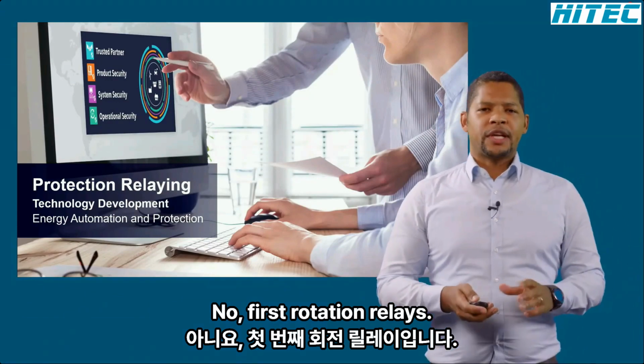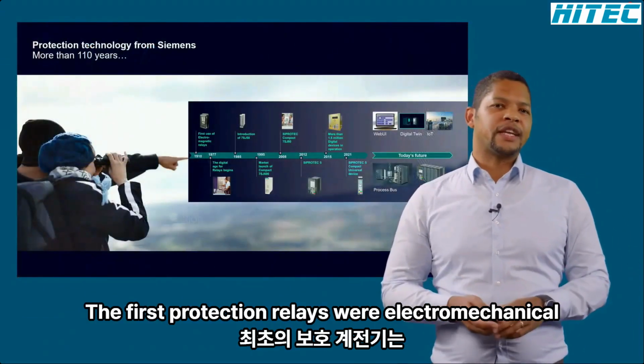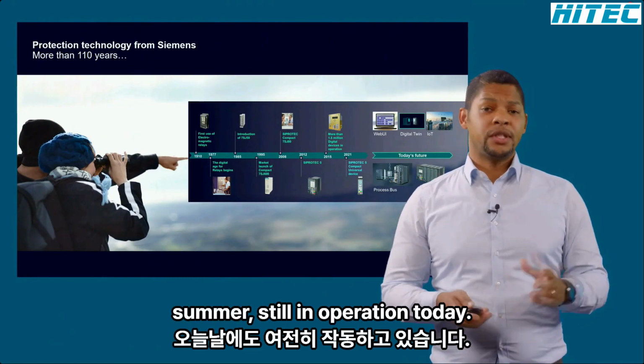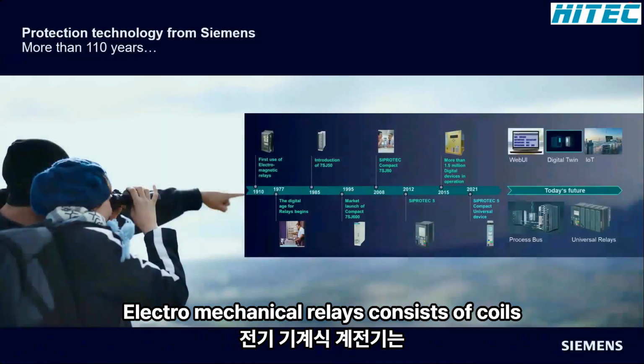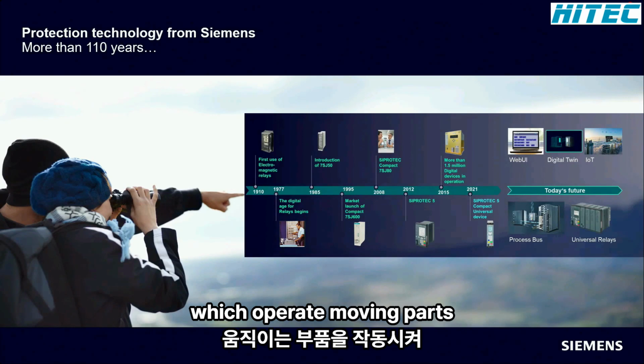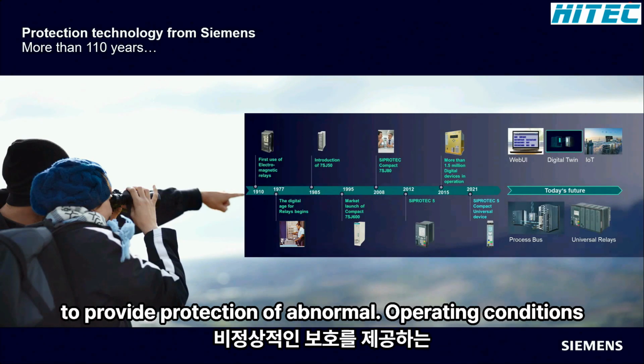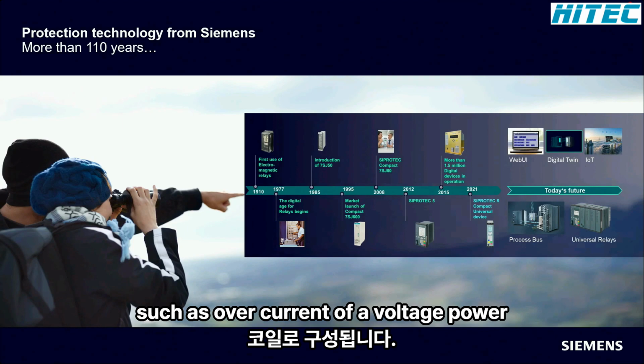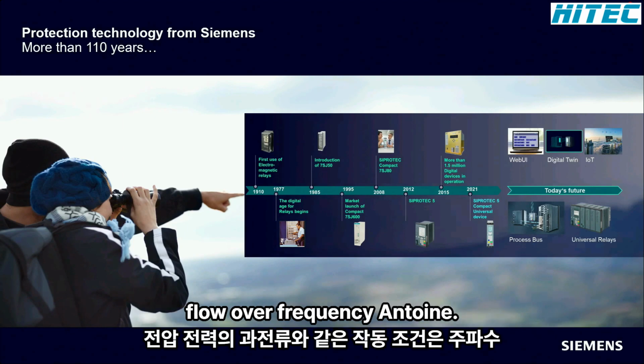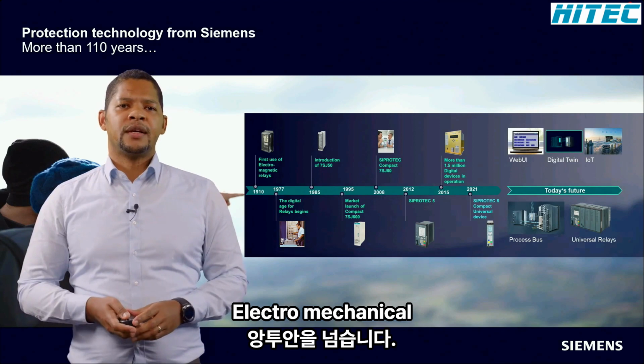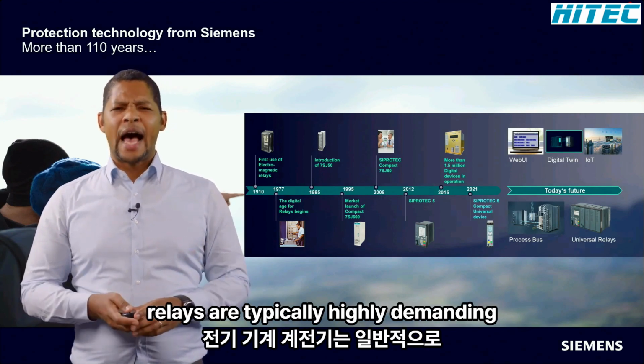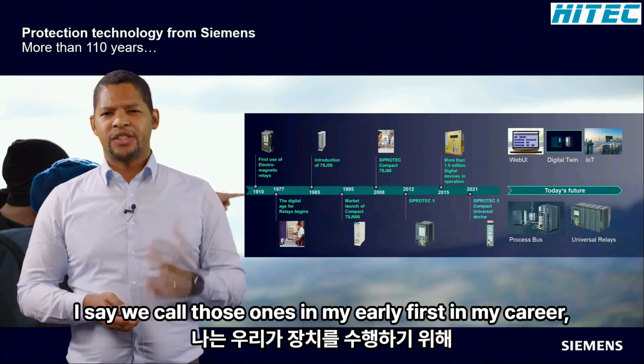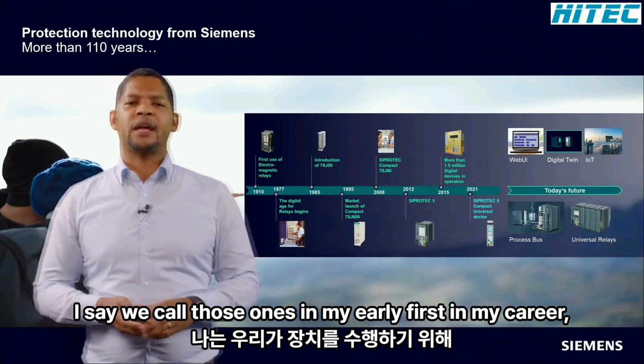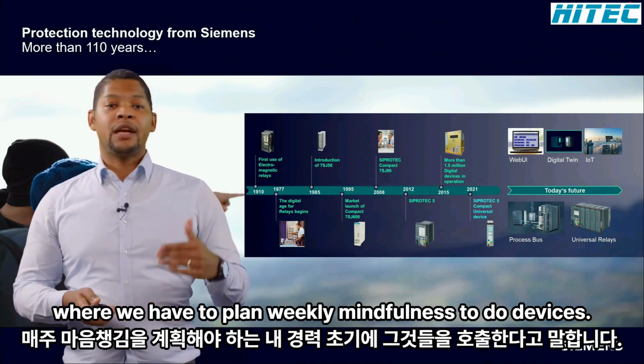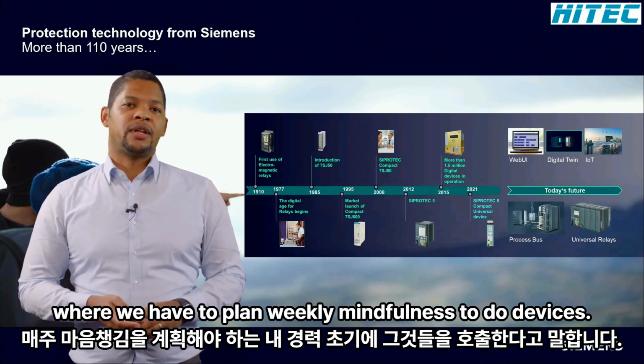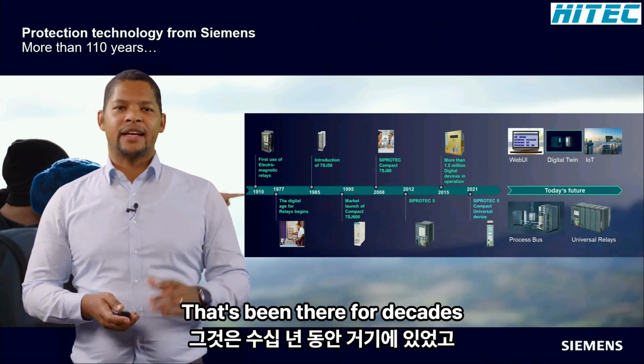Now, first, protection relays. The first protection relays were electromechanical devices. Some are still in operation today. Electromechanical relays consist of coils which operate moving parts to provide detection of abnormal operating conditions, such as overcurrent, overvoltage, reverse power flow, overfrequency, underfrequency, and so on. Electromechanical relays are typically highly demanding in terms of maintenance. I still recall those ones, in the early phase of my career, where we had to plan weekly maintenance for those devices that had been there for decades.